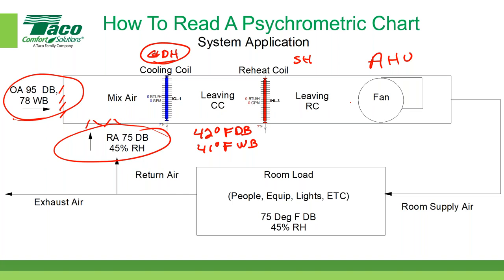And I'm going to reheat that air up to approximately 60 degrees Fahrenheit. And then I'm going to hit, this represents a duct over here. So that represents the room supply air. So my room supply air is going to be 60 degrees Fahrenheit dry bulb. And I'm going to show you in a psychrometric chart what that actual temperature and wet bulb temperature and relative humidity is going to be. Then it's going to pick up the room load.